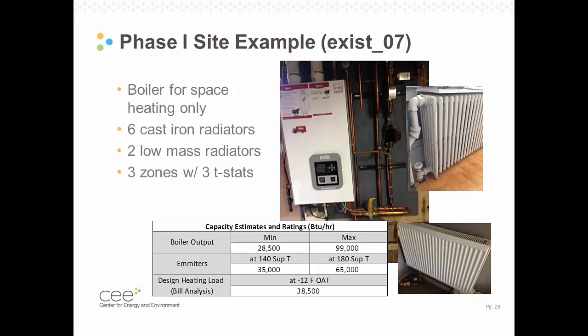So Site 7 provided a good example of this. You can see the picture of the boiler and a picture of some of the radiators. In general, we had a good high modulation on this boiler. You can see there the output range sort of between 100,000 BTU per hour and 28,000 BTU per hour.